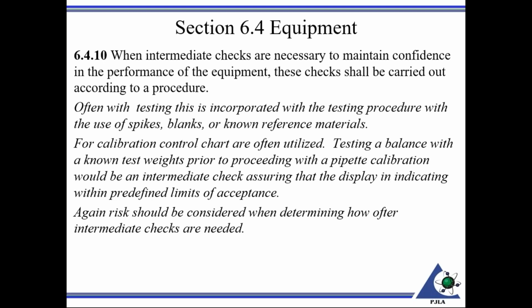For calibration, ideally, yes, control charts are often utilized. Say testing a balance with a known test weight prior to proceeding with calibration, particularly if you are doing an on-site pipette calibration, to assure that the display is indicating within predefined limits of acceptance. Again, risk can be considered when determining how often intermediate checks are needed.